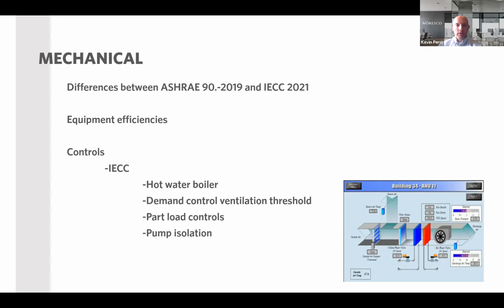IECC also has part load controls for hydronic systems over 300,000 BTU. And IECC also has pump isolation controls for chilled water plants. So these are the differences between IECC and ASHRAE; IECC basically has the majority of the differences here over ASHRAE. So let's talk about some of these efficiencies.